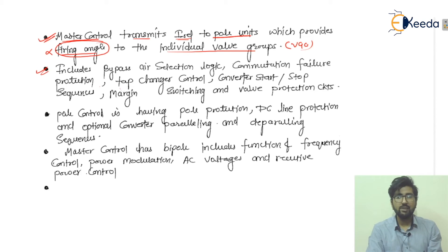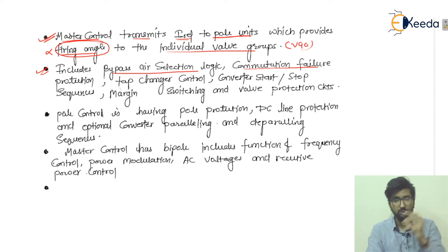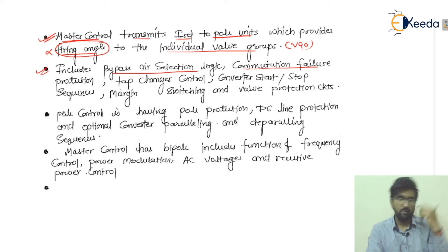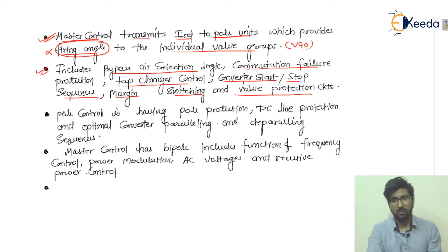The pole control also includes bypass pair selection logic. Commutation failure — which is the transfer of current from one valve to another within the same group, either the positive or negative group, upper or lower commutation portion — is handled here. Other functions include tap changer control, converter start and stop sequences, margin switching, and valve protection circuits.